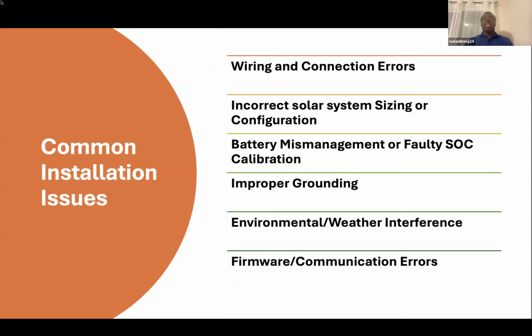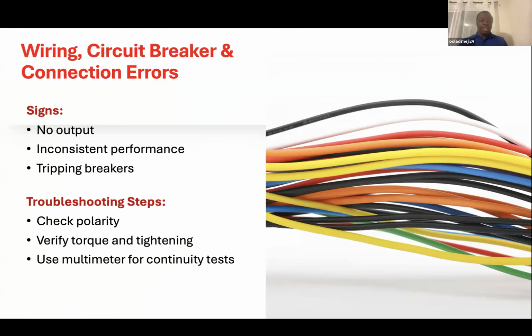Now, common issues that you see in installations: wiring and connection issues, incorrect solar system sizing or configuration, battery management, mismanagement or faulty state of charge calibration, improper grounding, environmental and weather interference, firmware and communications errors. So I'll take these one after the other. For wiring, circuit breakers, connection errors, what are the signs that you know there is a problem? When you have no output, inconsistent performance, tripping breakers.